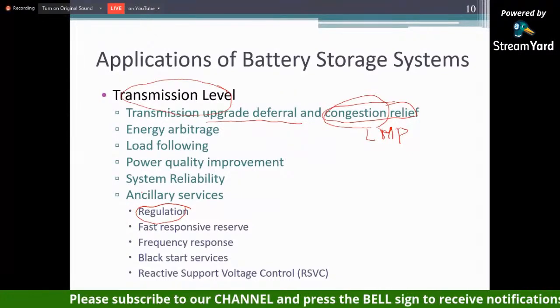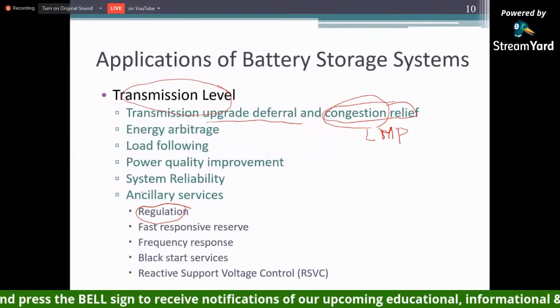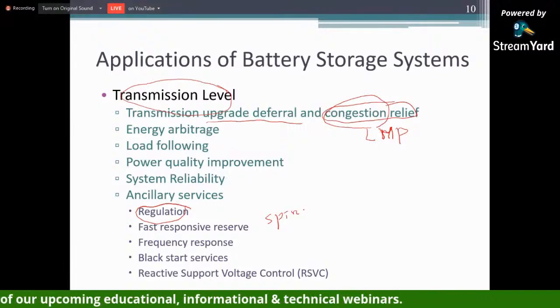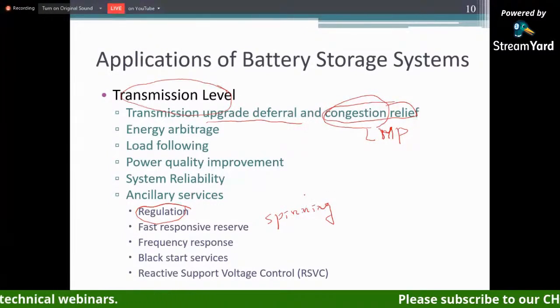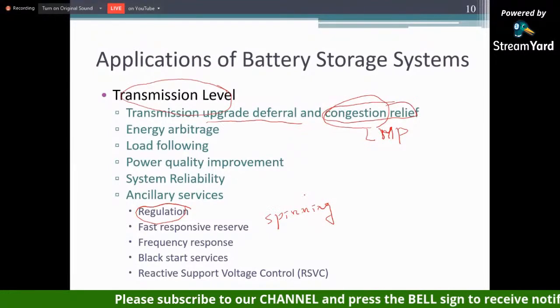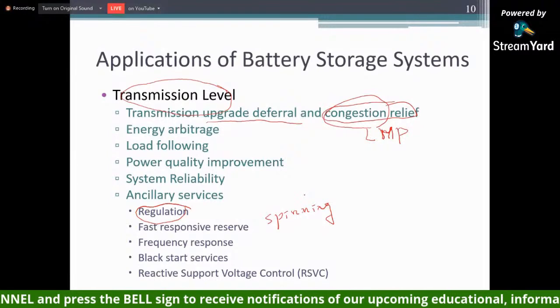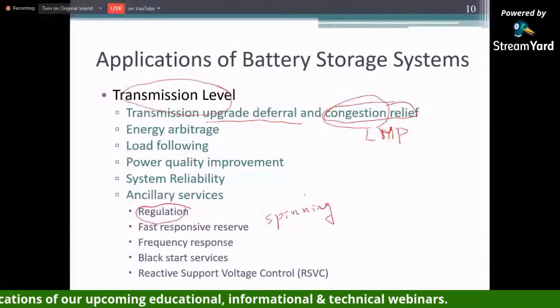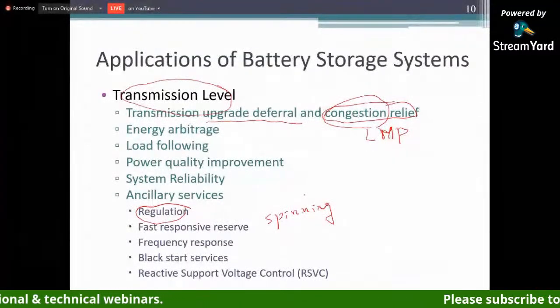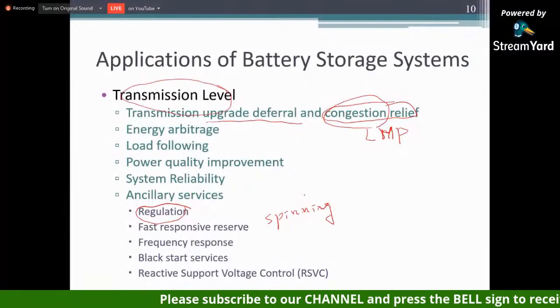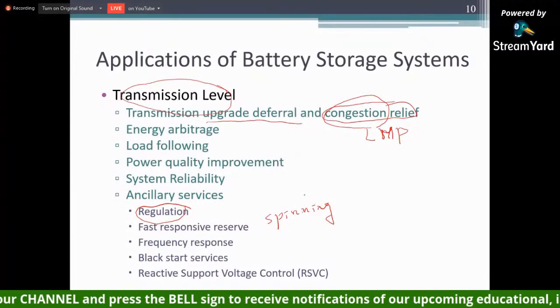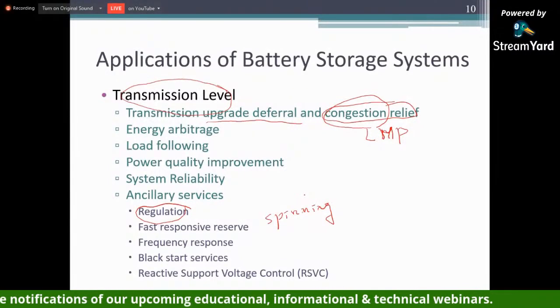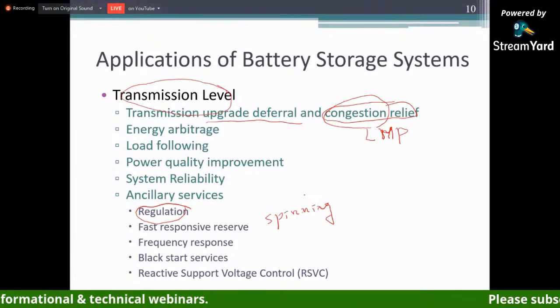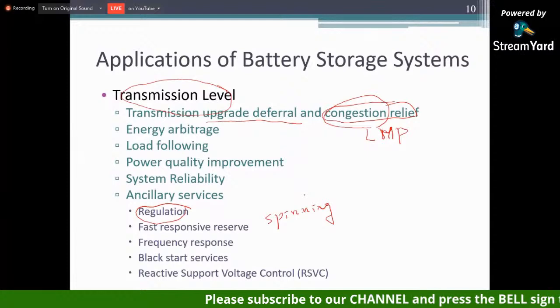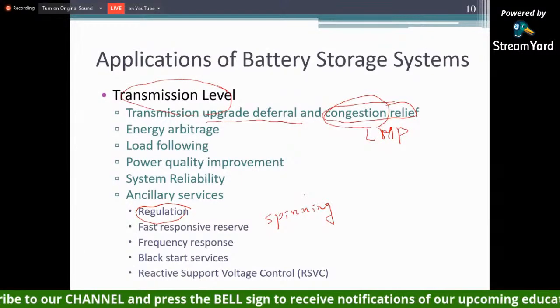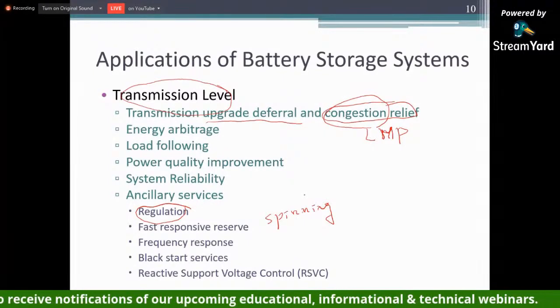From the regulation service part, traditionally we call it a spinning reserve. Traditionally all those reserves come from the generator. The reason we call it a spinning reserve is because the generator is spinning, but we don't allow it to produce full rated capacity. They always reserve something to support the system in case an incident happens that requires more generation. That way, some of the generator's capacity is withheld, which is why we call it the spinning reserve.